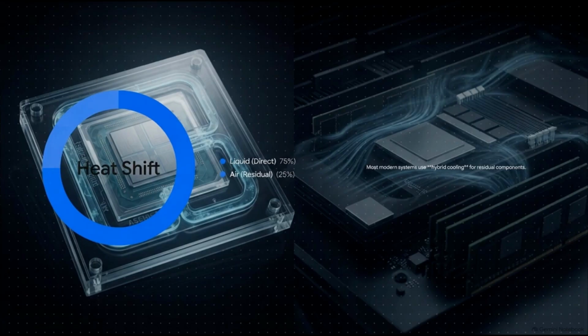It's important to note that while liquid is doing the heavy lifting, removing 70 to 75% of the heat directly from those massive GPUs and CPUs, most modern systems are still hybrid. We still rely on a small amount of perimeter air cooling, maybe 25 to 30%, just to handle residual components like memory, drives, and power supplies.